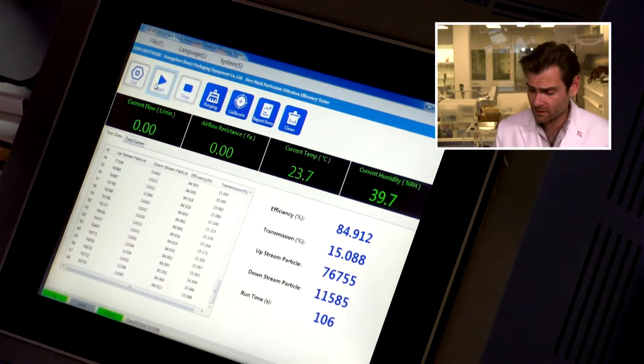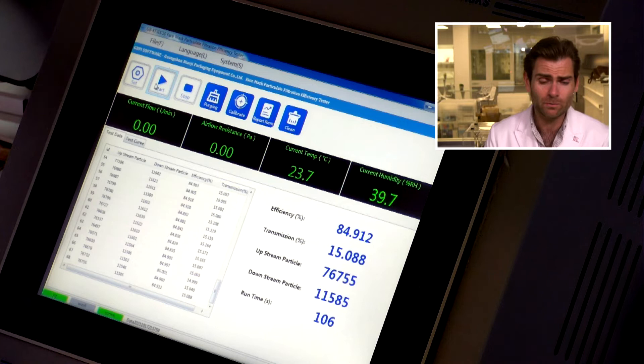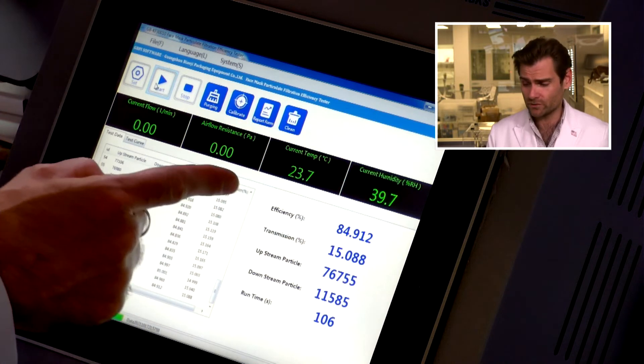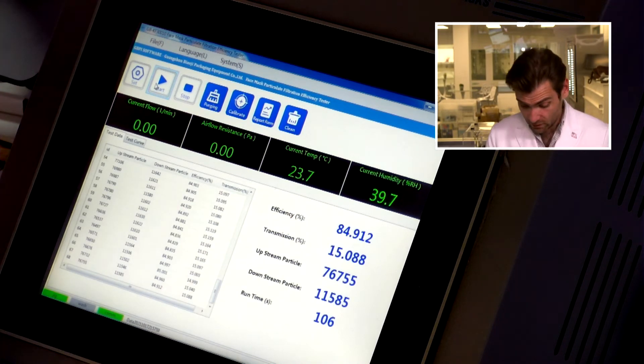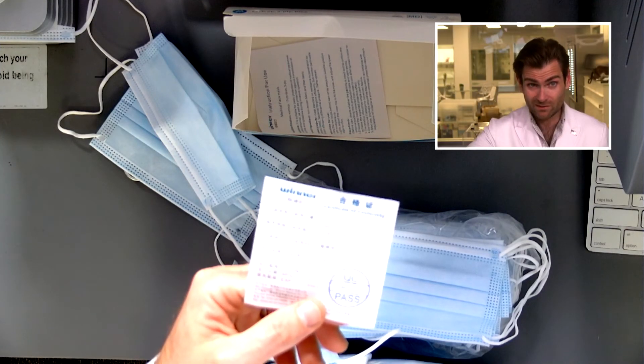There is variability from test to test — things are different depending on humidity and storage of the masks. We bought these on Amazon, and maybe Amazon didn't properly store them before they got to us. But a shift of 10 points is way too much. I don't think these were hitting that number. Production date — this was produced last July of 2020, and the expiration date isn't until 2023. So if their expiration dates are accurate, it should maintain that filtration until then. But we're off by about 10 points.